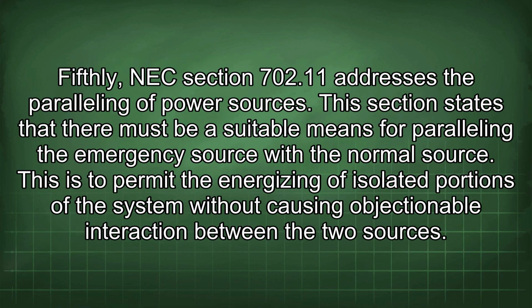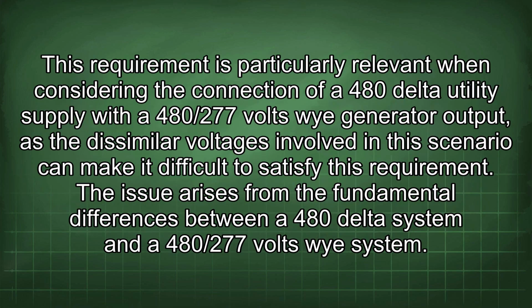Fifthly, NEC Section 702.11 addresses the paralleling of power sources. This section states that there must be a suitable means for paralleling the emergency source with the normal source. This is to permit the energizing of isolated portions of the system without causing objectionable interaction between the two sources.